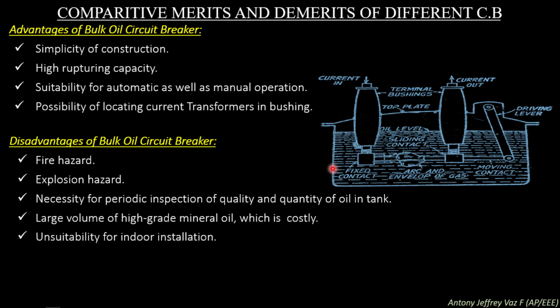Unsuitability for indoor installations. This type of circuit breaker has a fire hazard, so it should be mounted outside of the power yard. If a fire breaks out, it can be extinguished with the help of a fire extinguisher present outside, or you can call a fire service to stop the fire and prevent more damage to the power system. So this type of circuit breaker should be installed outside.